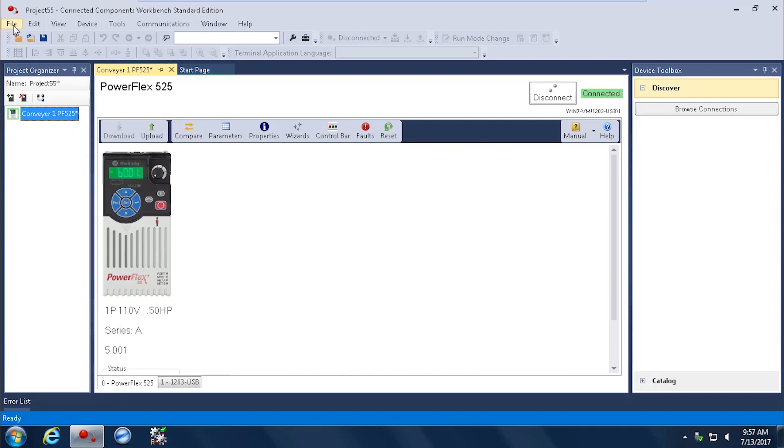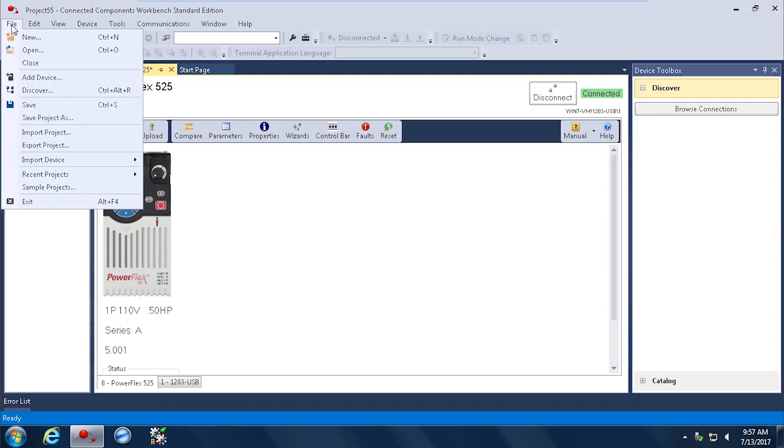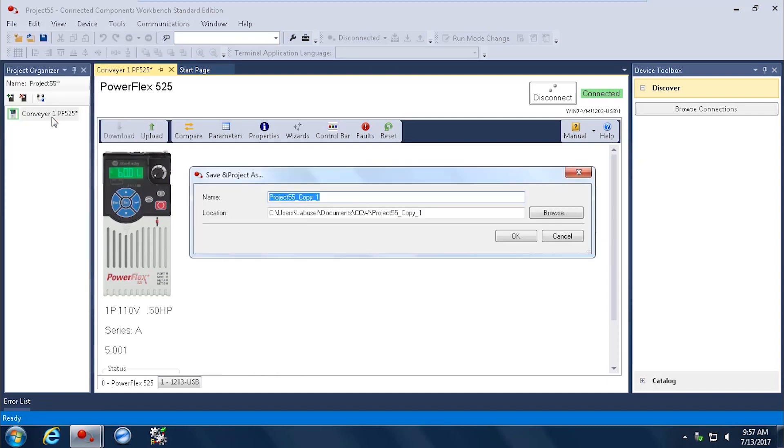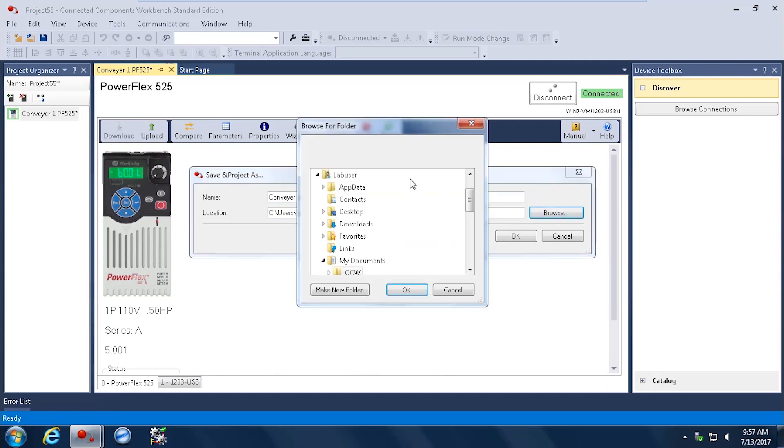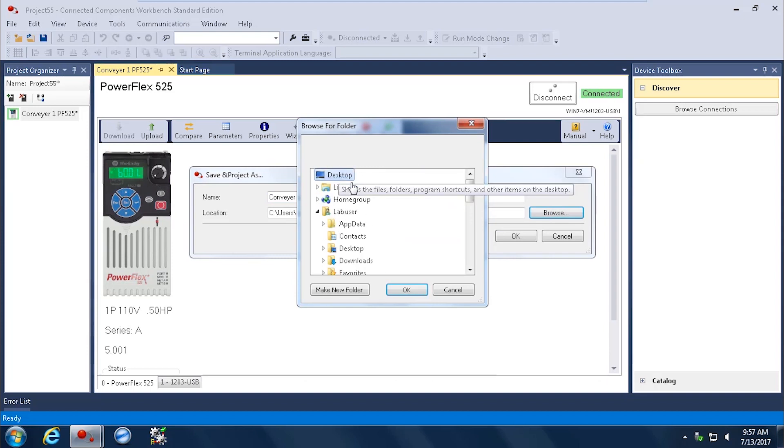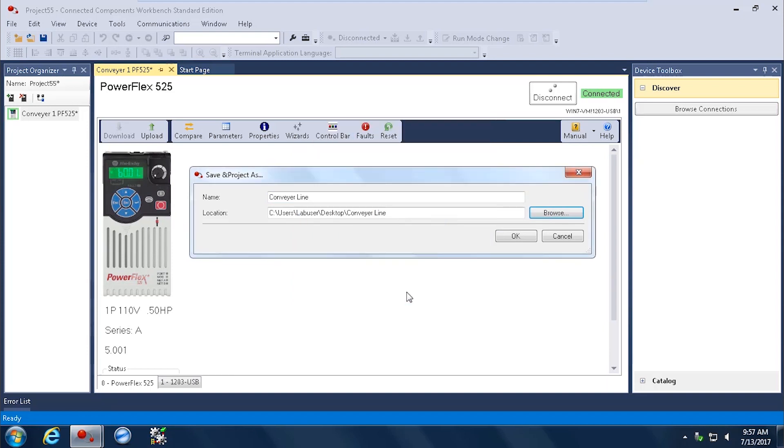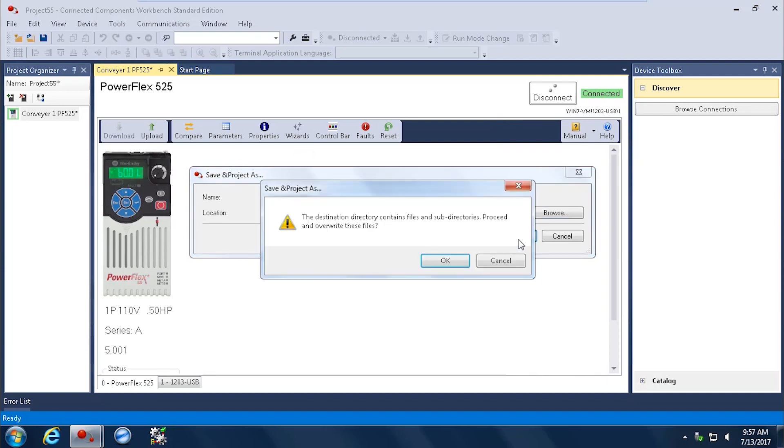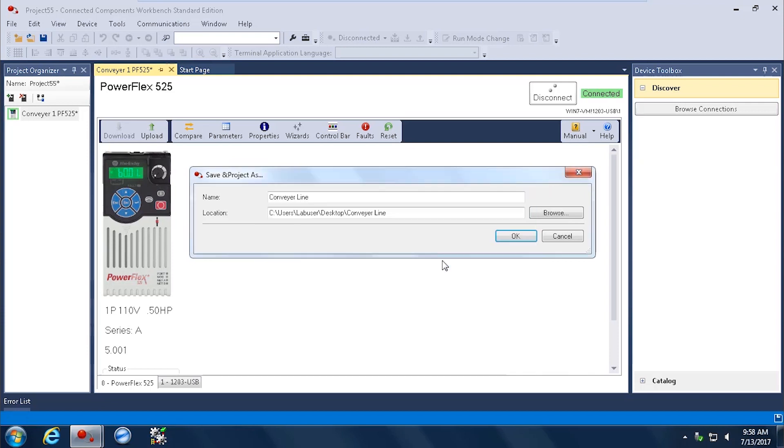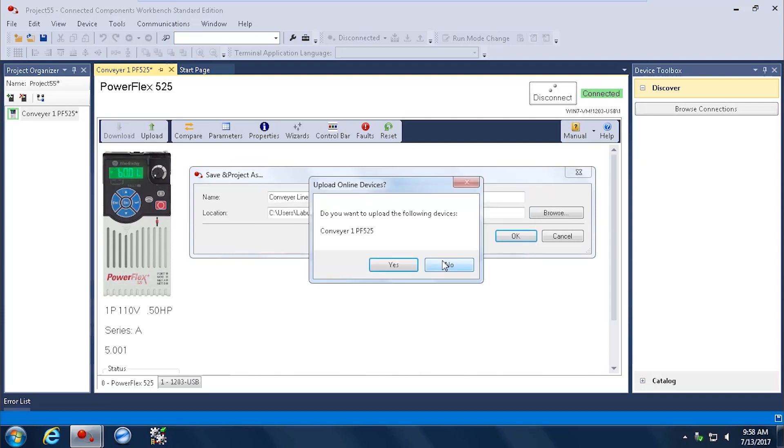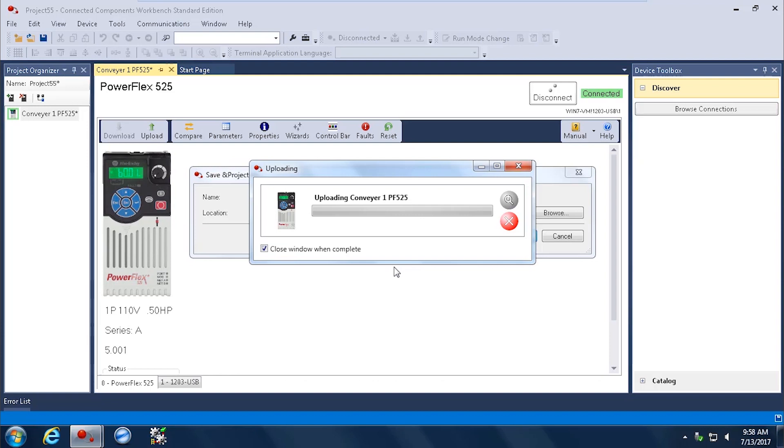Now I can go ahead and select File at the very upper left corner, and I can save my project as some name for the project. I could have multiple drives in this project. In this case, I have my one drive, Conveyor1PF525. And I'm going to name the project Conveyor Line. That's my overall project name. And I'm going to save it to my desktop. So I select Desktop. Select OK. Select OK once again. And I'm going to go ahead and proceed to overwrite any files I may have had. If I had called this before, or if it's a new project, you won't get that anyway. It'll just upload. So now I'm uploading everything from that drive into that file, Conveyor Line, with my drive called Conveyor1PF525.